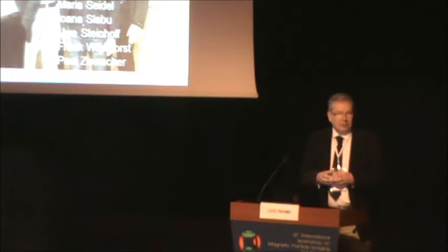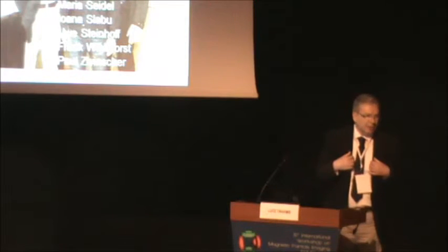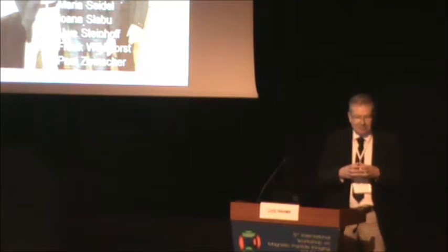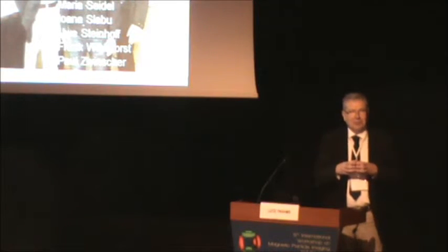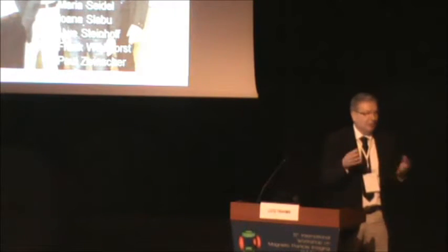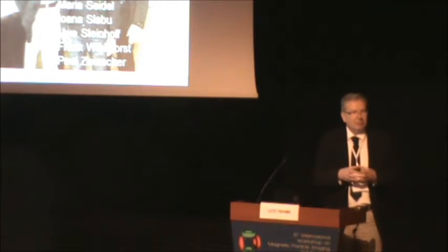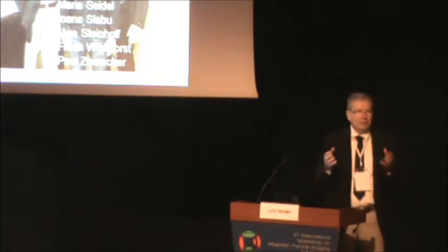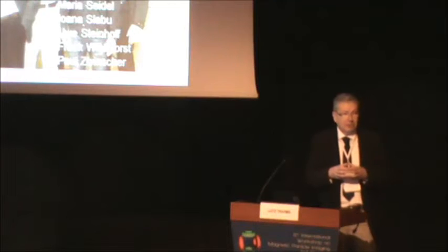And then, well, at PTB we are in a very lucky situation that we have colleagues who are experts in SQUID development. We do not develop the SQUIDs in my group. They were so nice to develop SQUIDs which are extremely insensitive to high fields. I mean, they're robust against high fields, they can measure as well, but they have a particular design that makes them robust, and this is the final solution to this problem. So we are on the safe side now in this respect, but it has been a real challenge to this group.